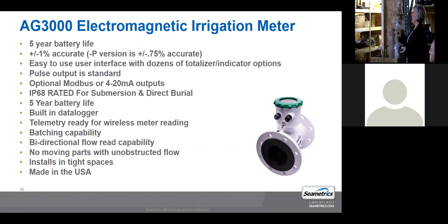This meter has a 5-year battery life. It's plus or minus 1% accurate on the standard version. The P version has a 0.75% accuracy. This one's really a neat meter because the dial face is super easy to use. If you had ordered this meter in gallons per minute, and then you wanted to set it up in acre inches by gallons per minute or cubic feet by cubic feet per second, it can all be done right at the head there. Pulse output changes can be done. It's password protected. You can't reset the total ever, but it'll convert your total over to whatever units of measure that you've changed it to.